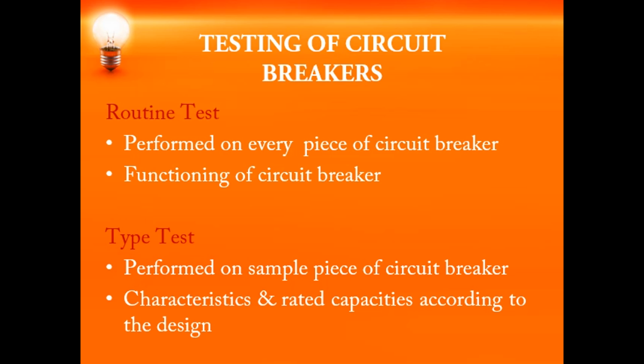So what is meant by this routine test? Routine test means it is carried out on every piece of circuit breaker. Say you have a lot of, say, 20 to 25 circuit breakers. So all those 20 to 25 circuit breakers will be tested. Okay. So why is it done? The routine test is mainly done to confirm the proper functioning of the circuit breaker. That is why it is performed on each and every piece of circuit breaker.